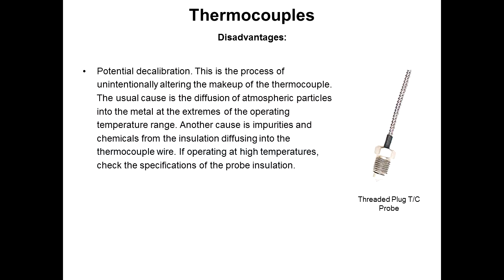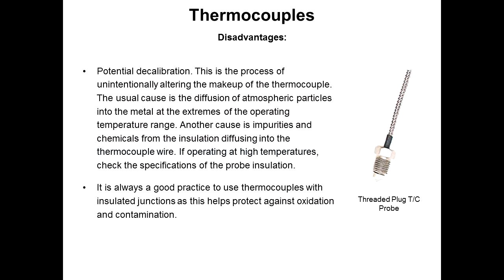Potential decalibration is the process of unintentionally altering the makeup of the thermocouple. This can be caused by diffusion of atmospheric particles into the metal at the extremes of the operating temperature range. Any thermocouple that operates above 2,000 degrees needs to have the sensor shielded inside of glass or quartz, because the oxygen will corrode it terribly and it won't last very long. It's always good to use insulated junctions where possible when you're making thermocouple connections, to protect them against oxidation and contamination.